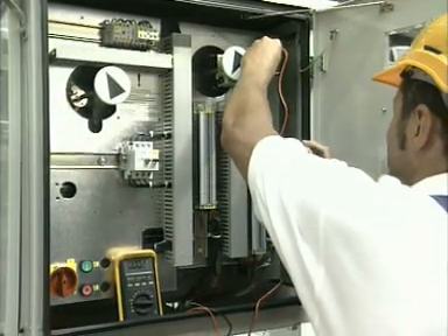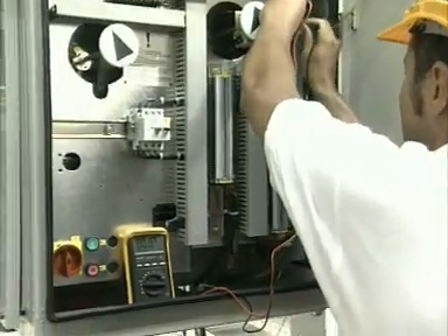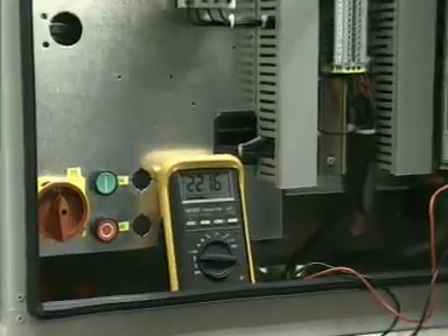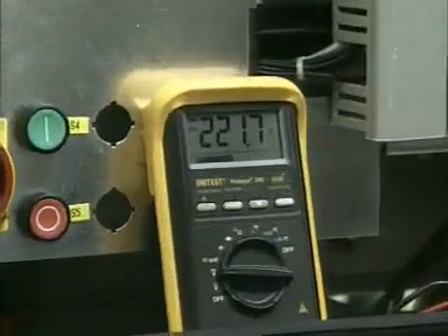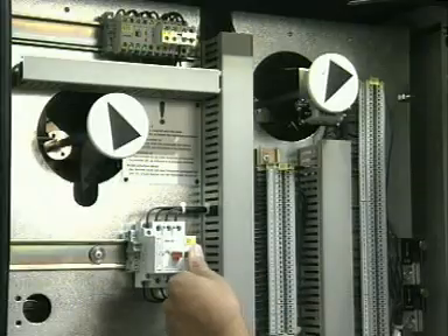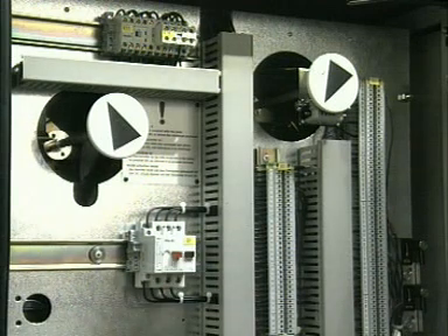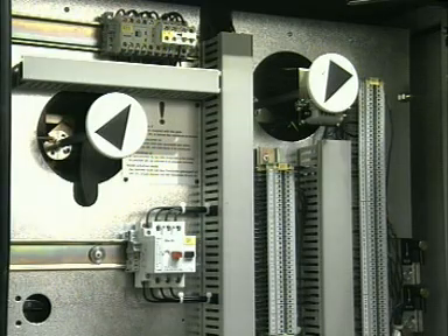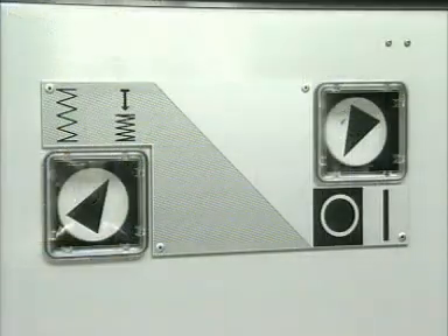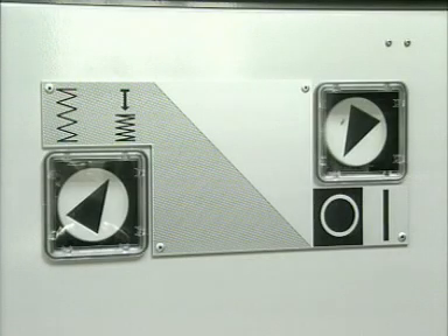Now the supply voltage can be applied. When the motor protection switch is turned on, the motor begins to charge the closing spring. As soon as the spring is charged, the motor circuit will automatically be interrupted by the motor limit switch. The position display for the closing spring indicates that the spring is charged.